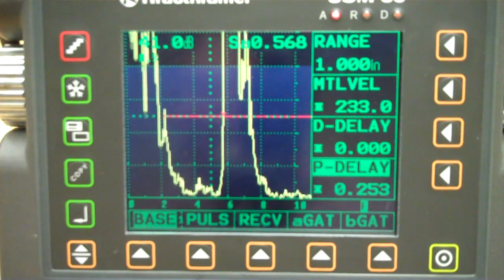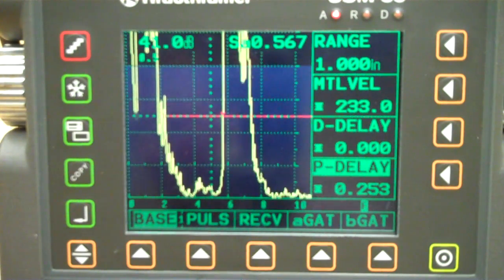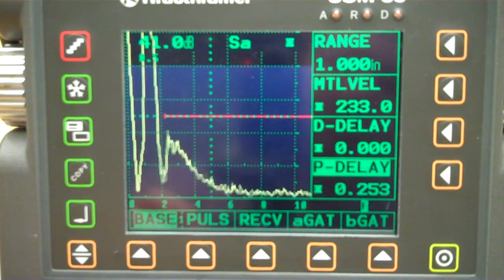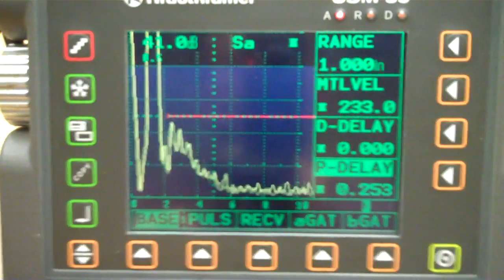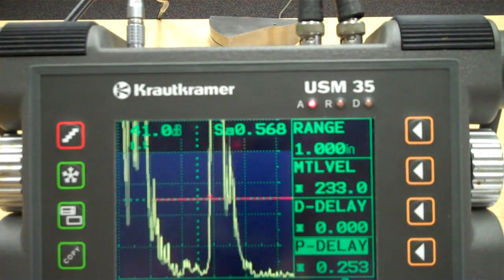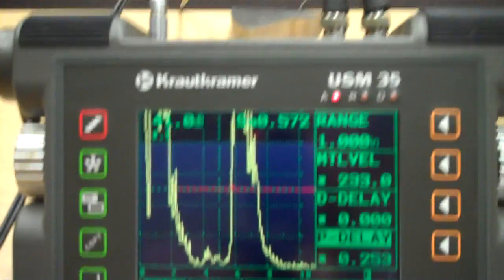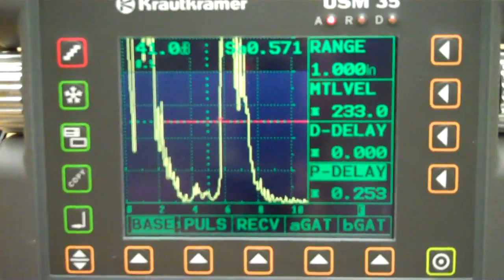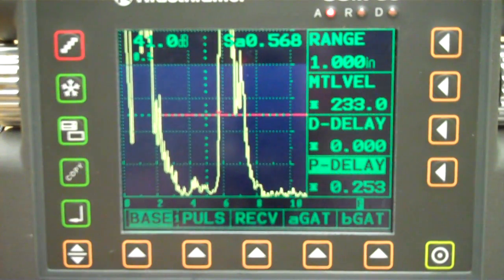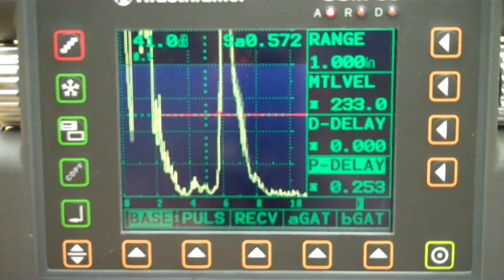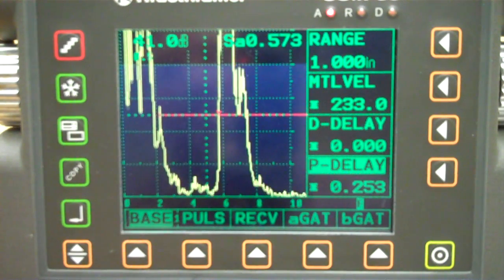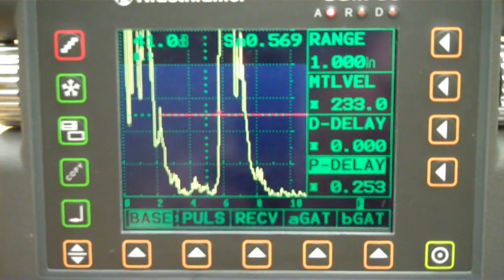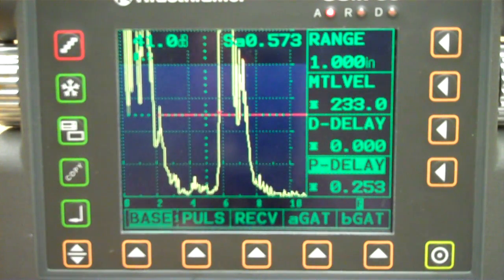So if I just plunk this down without doing anything else, let's just see what happens just for fun. I'm just putting this on my 1-inch block here. Let you look down here real quick. Here I am, I'm just on my 1-inch block. That's off the block. There's the transducer. Now it's on the block. So we need to see what kind of difference that makes. Off, on. Now we know that we have a dual element transducer, but we haven't changed any of the settings to actually tell the scope that we have a dual element transducer.